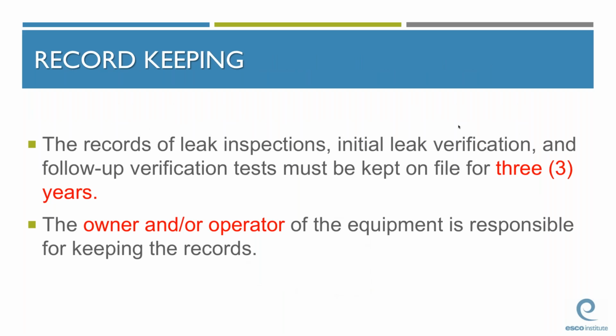Another important change to the EPA regulations involves record keeping. All leak inspection records must be kept on file for a minimum of 3 years. And it's the owner and/or operator of the equipment who's responsible for keeping these records. These records include initial leak verification tests as well as follow-up verification tests.